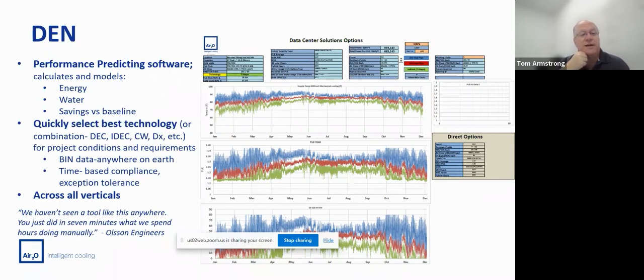So it's going to be called DEN for a while. But it does performance predicting for energy and water, can calculate savings versus baseline, and we can determine the best cooling approach for a given project in a given part of the world—comparing DX cooling, IDEC, chilled water, or any other approach—and determine hour by hour how close we're staying to target temperatures for supply air and room air, providing a basis for making decisions.